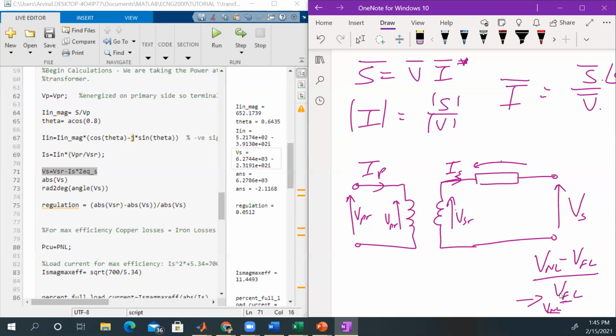But the transformer is really a through device: power in equals power out, and you're just transforming the voltage and current. So there's one power factor or one apparent power rated for the transformer. Traditionally, they would say if you take that power and use the primary voltage, you get the primary rated current, and if you divide that same power by the secondary voltage, you get the secondary rated current. But that itself is a big approximation because the core loss is there.